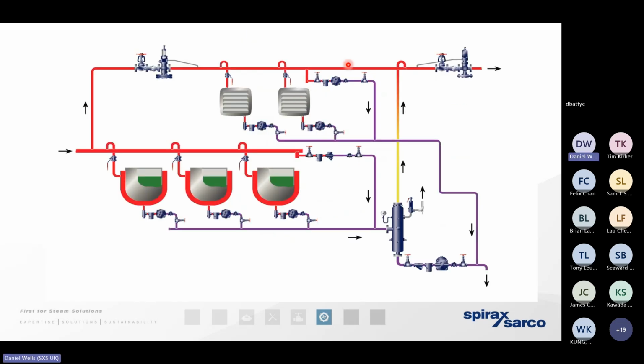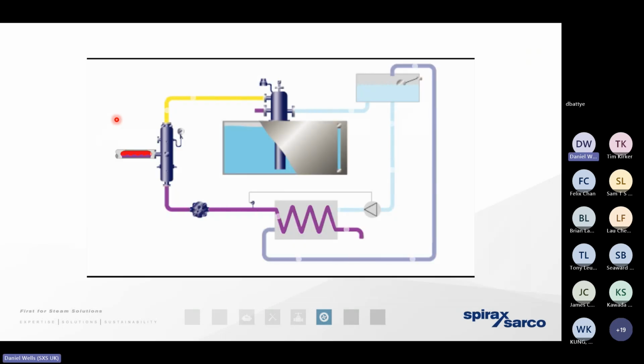In other processes, we can take the flash steam that is produced as a result of that condensate depressurization, and we can divert it back to a completely different, unrelated process. Or in the boiler house itself, any high temperature hot water that depressurizes, for example, when we take that water out of the boiler to go to waste, any steam that's produced as a result of that water depressurizing is going to be reasonably clean. It's not going to have too many chemicals in it. So it's in a perfect condition for being diverted back to the hot well to help us elevate the water temperature that's there in demand for steam production.